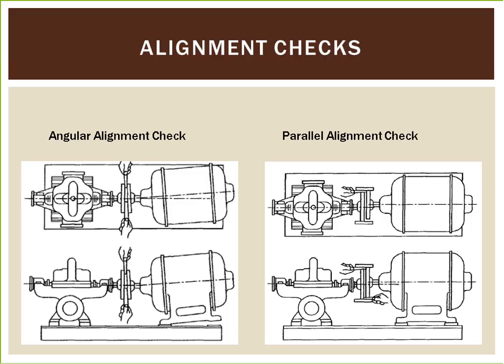A check for angular alignment is made by inserting the taper gauge or feelers at 4 points between the coupling faces and comparing the distance between the faces at 4 points spaced at 90 degree intervals around the coupling. See the figure on the left.